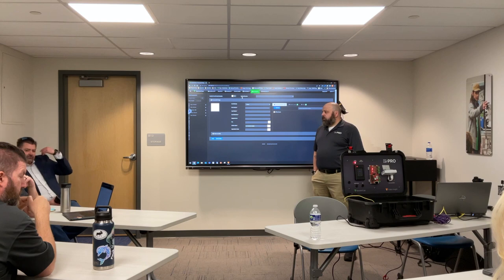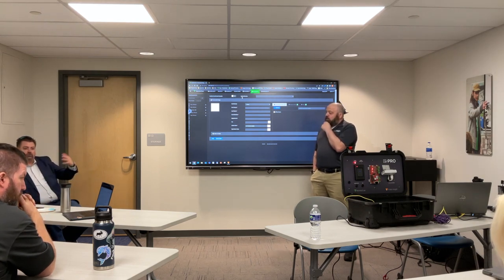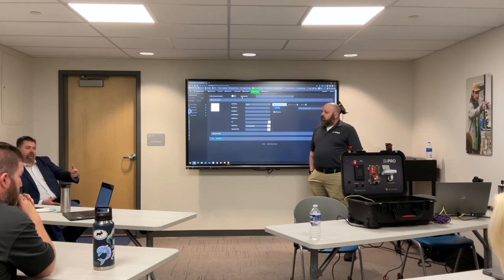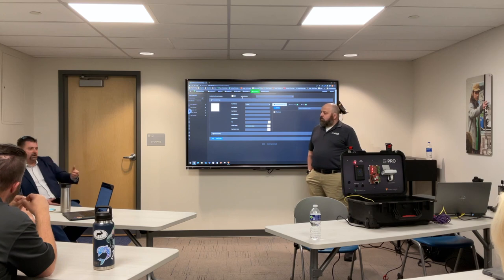Yeah, so when I hear emergency, that's why I asked. Of course. What do you mean by emergency alert systems? My default is fire alarm. All that stuff is really just a dry contact into the system, so you can unlock all the doors or lock the system. You could have a button in a teacher's office if they have a threat, they hit a button or some type of interface by just a contact closure. And that's how access control really integrates, by contact closure.